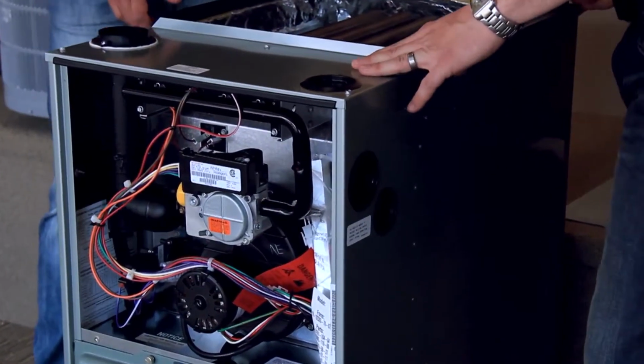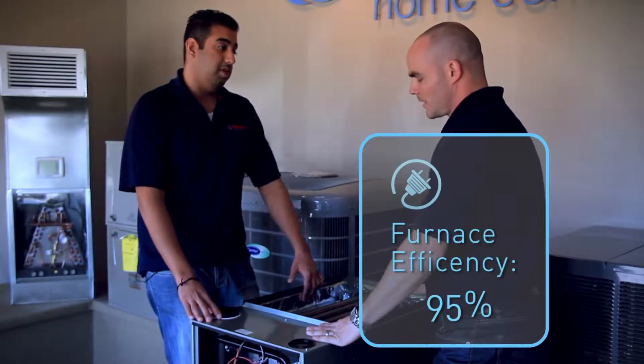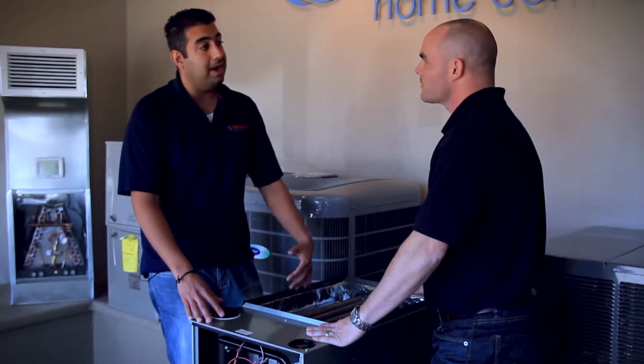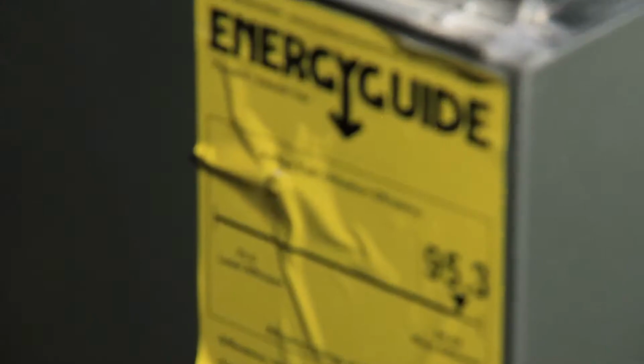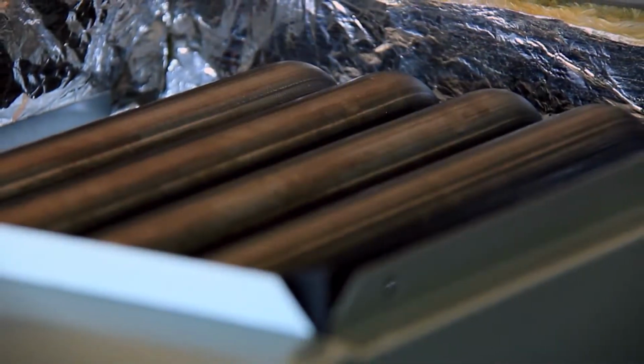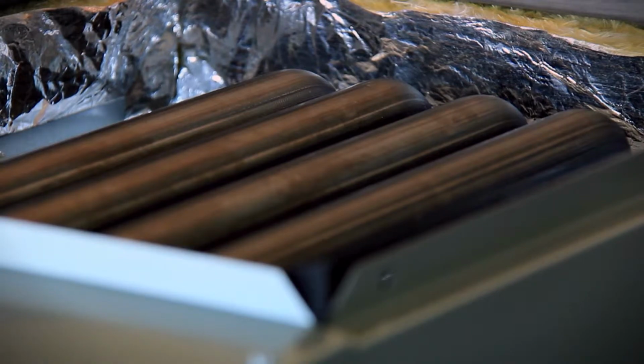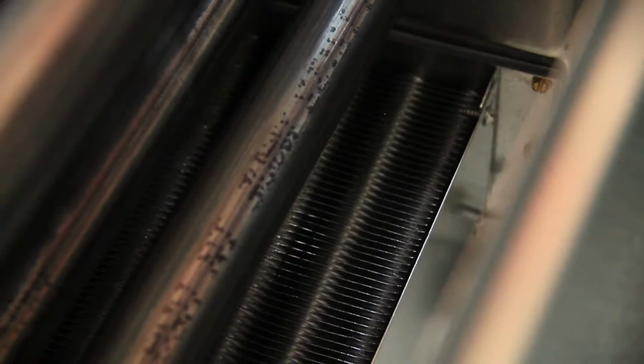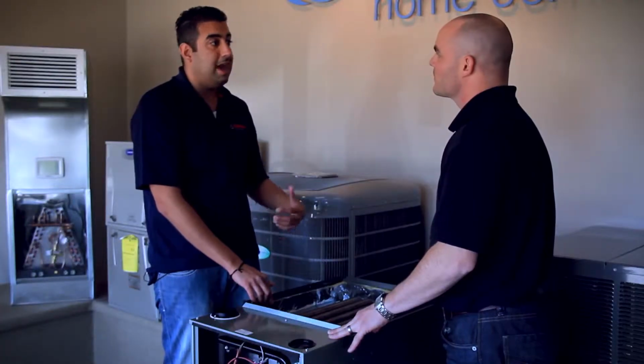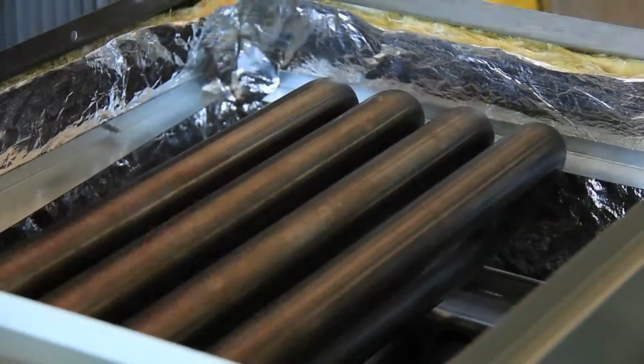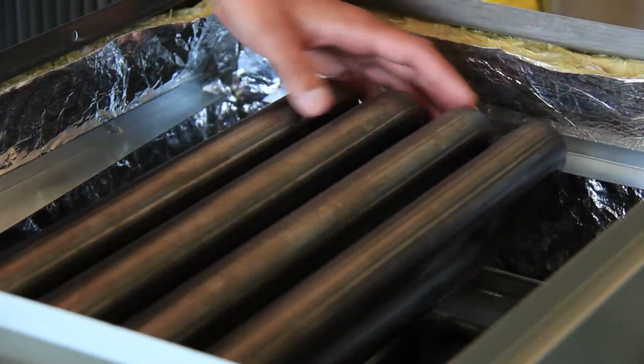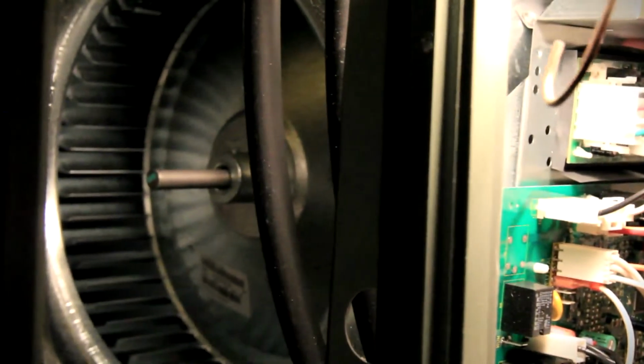Cliff, this is a high efficiency furnace. It's 95% efficient, where the older furnaces used to be 60% or 80% efficient. So what that means is basically utilizing 95 cents to the dollar to warm your house. What makes it high efficiency is there's two parts to it. One is a primary heat exchanger, as you can see. Okay, yeah. And there's a secondary heat exchanger. And these whole components are basically made out of stainless steel, where in the olden days the older furnaces that were 60 or 80% efficient were cast iron. Okay. Burners light up, fumes go into the primary heat exchanger, and they work all the way to the bottom to the secondary heat exchanger, where this motor is basically pulling out flue gases.